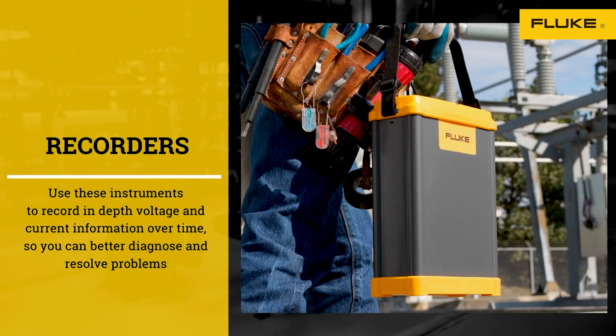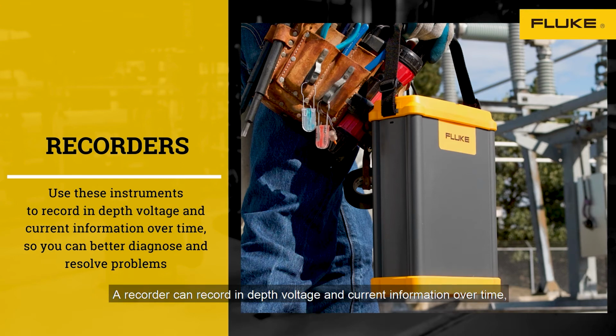Recorders: many problems can't be found immediately, especially those caused by different loads interacting. Intermittent voltage disturbance or high-speed transients are also hard to detect. A recorder can record in-depth voltage and current information over time, so you can better diagnose and resolve problems.